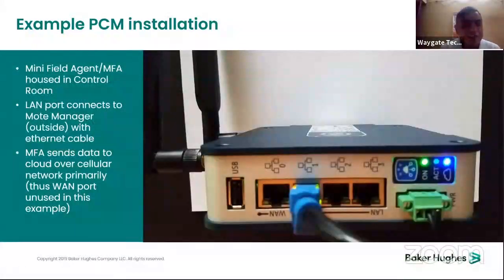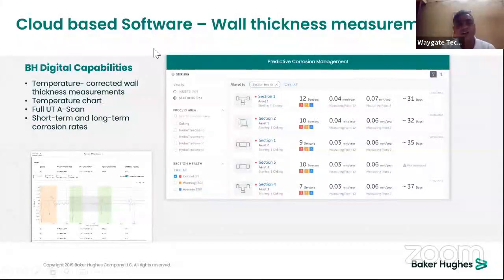The Mini Field Agent housed in the control room connects via LAN port to the Mote Manager outside using an Ethernet cable. It sends data to the cloud over a cellular network. The cloud-based software provides temperature-corrected wall thickness measurements, temperature charts, full UT A-scan data, and short-term and long-term corrosion rates. The system predicts corrosion rates three months in the past and forecasts the next three months, helping customers decide when to repair, replace, or continue operating.